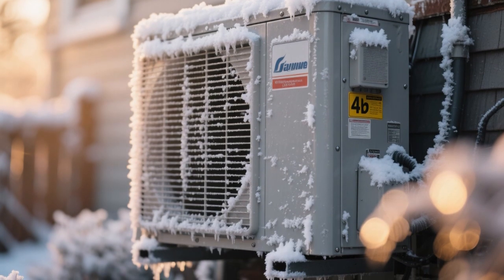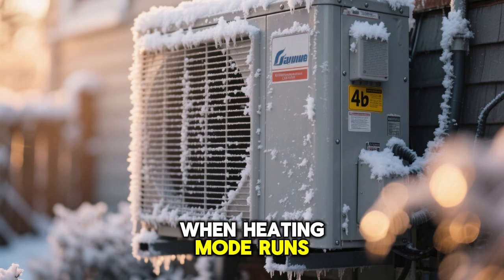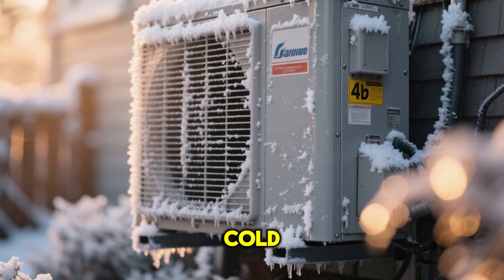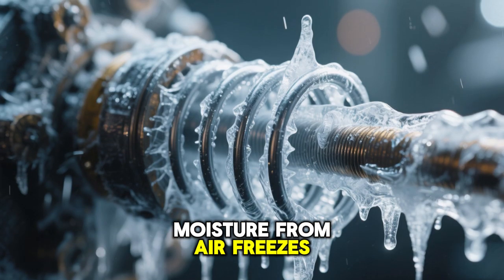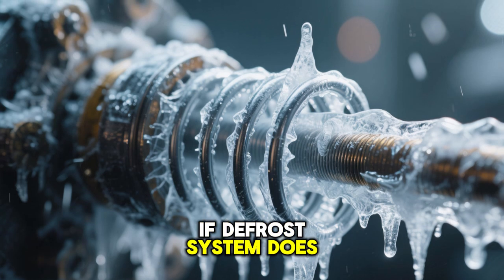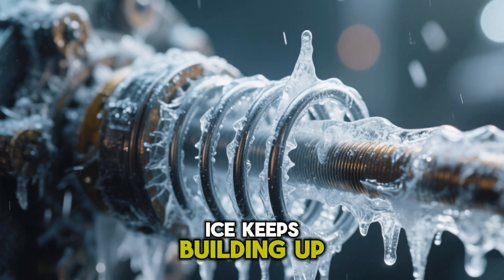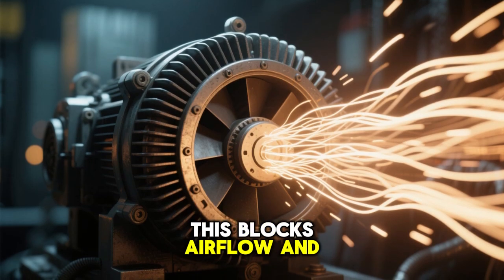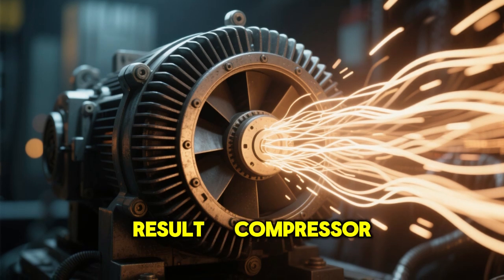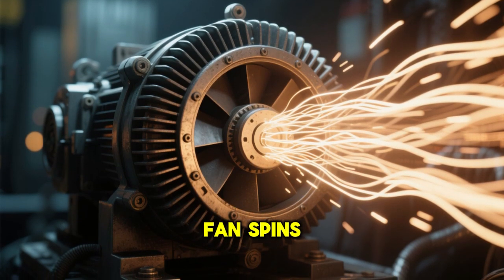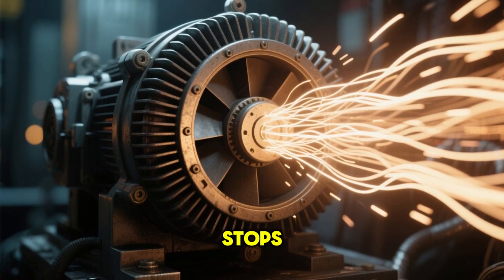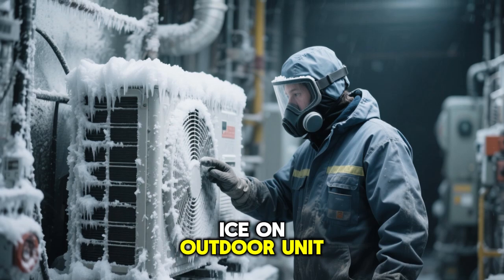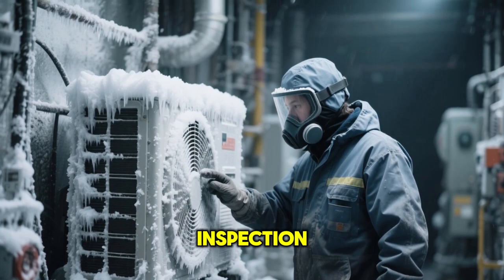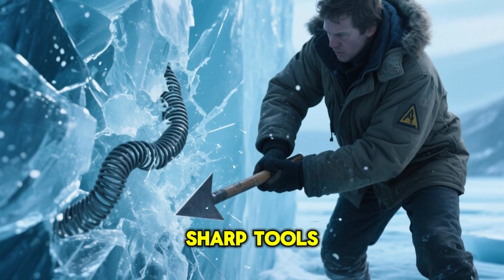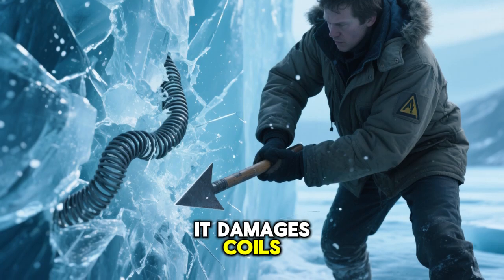Another serious winter issue is ice buildup. When heating mode runs, the outdoor unit becomes cold. Moisture from air freezes on the coil. If the defrost system does not work properly, ice keeps building up. This blocks airflow and heat transfer. Result: compressor runs, fan spins, but heating stops. If you see thick ice on an outdoor unit, your AC needs defrost inspection. Never break ice with sharp tools, it damages coils.